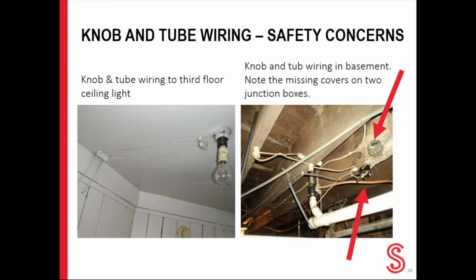The fires usually start when the wiring is covered by insulation, because knob and tube wiring was designed to be installed in a free air environment so that it can dissipate the heat that it produces. This is especially true in attics and walls with insulation, because the heat that's generated, the higher temperatures, weaken and damage the wiring, setting the stage for a structure fire.